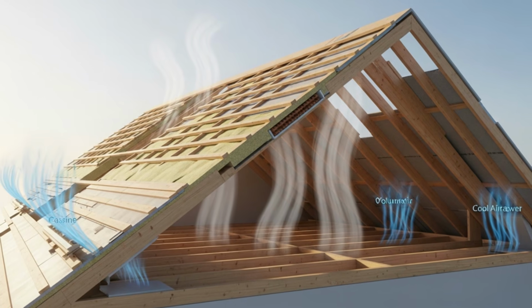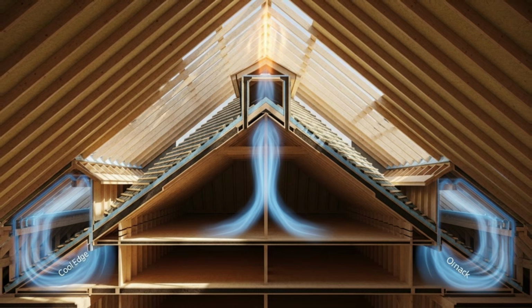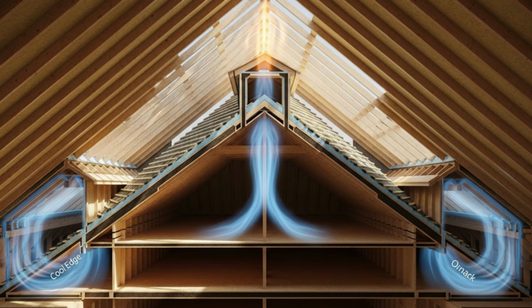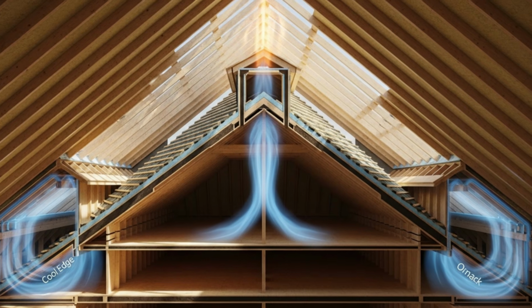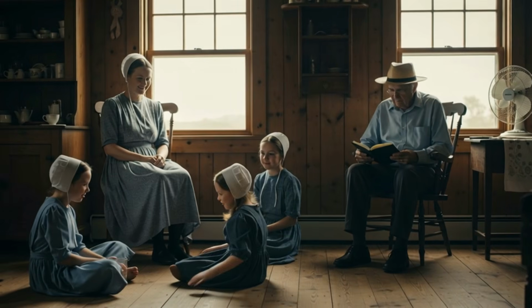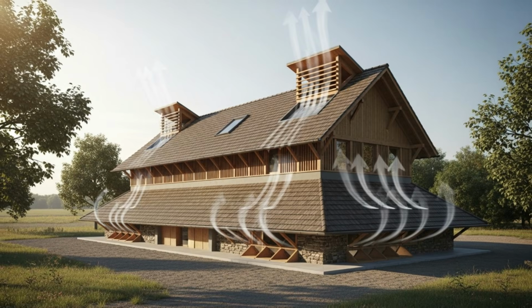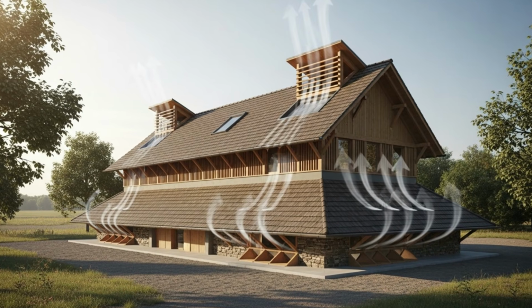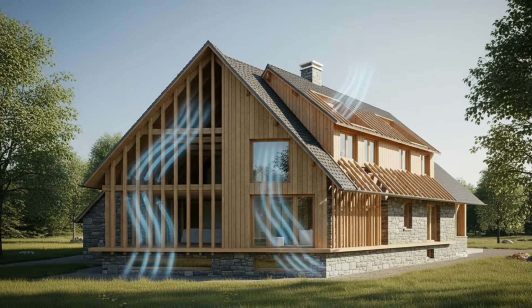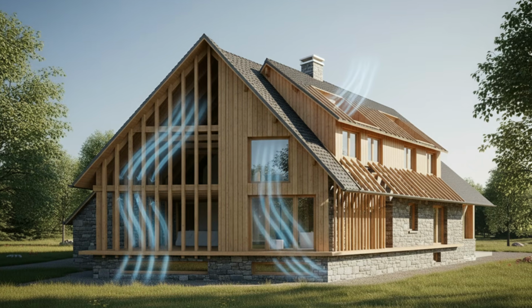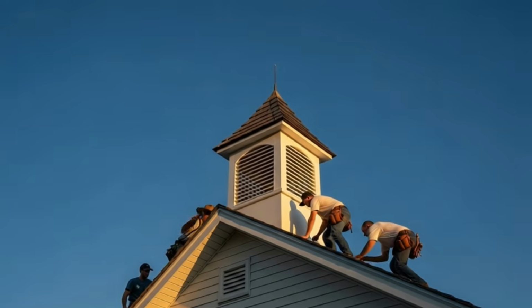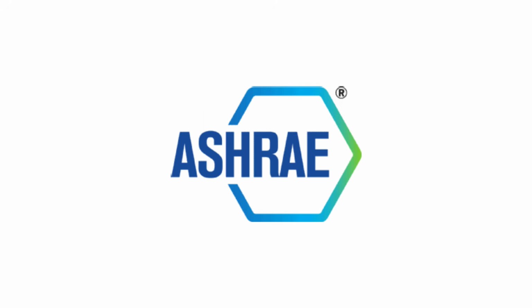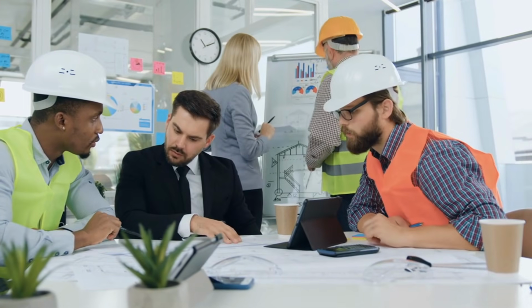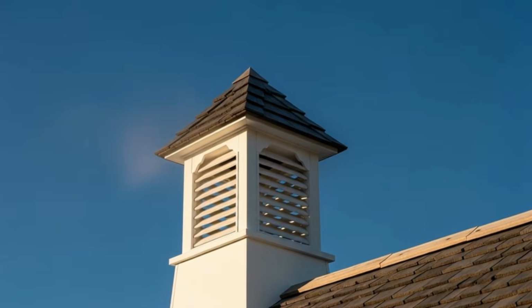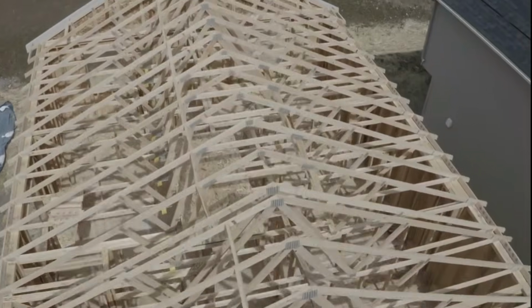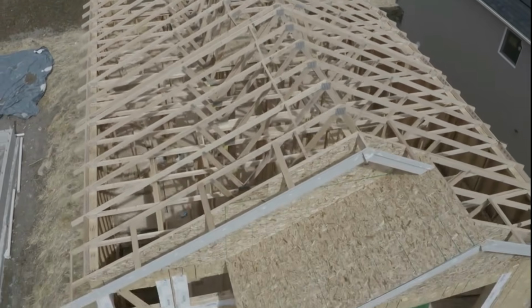It does not distinguish between a 4 to 12 pitch with 2 passive soffit vents and a 12 to 12 pitch with a 4-sided louvered cupola, a design that produces dramatically more airflow per hour. The code does not prohibit the Amish approach. It simply does not recognize it. There is no line item for passive stack effect cooling via steep pitch attic and cupola ventilation. There is no credit for eliminating the need for mechanical cooling. There is no checkbox, no category, no calculation method approved by ASHRAE or the ICC that a builder could use to demonstrate that a properly designed attic cupola system meets or exceeds the comfort performance of a 14-SEER air conditioner. No conspiracy, no ban. Just a code that never included it.